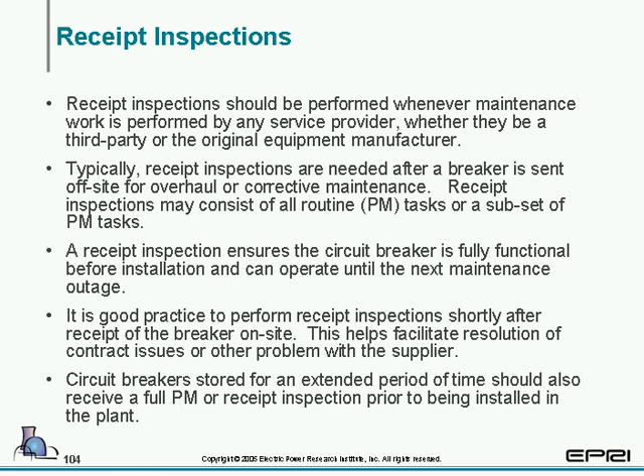Also, if you're lucky enough to have spares and you store spares for an extended time, maybe in a storage facility, before you pull that breaker out and stick it into a plant, it's also good practice to do a PM, either a full-blown PM or just check the breaker out.